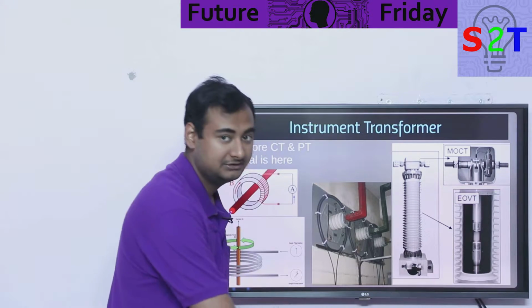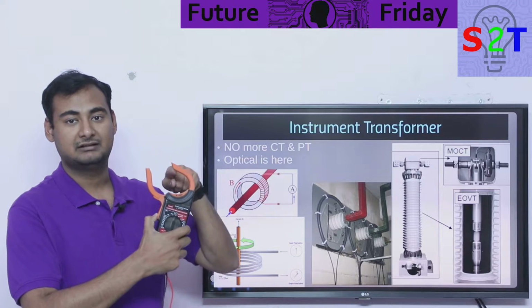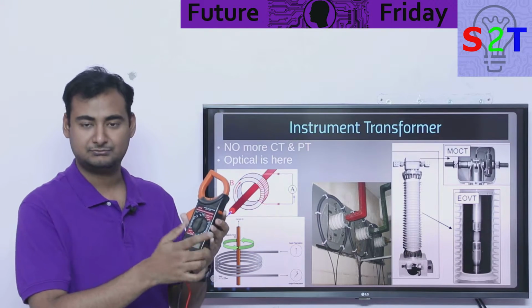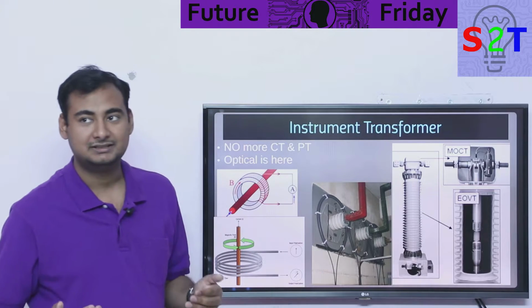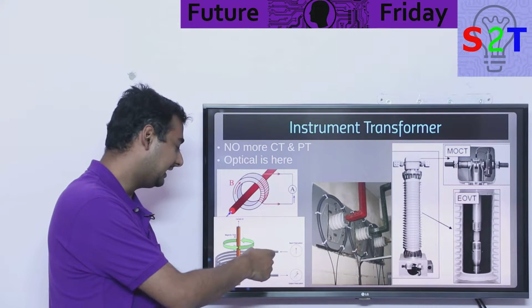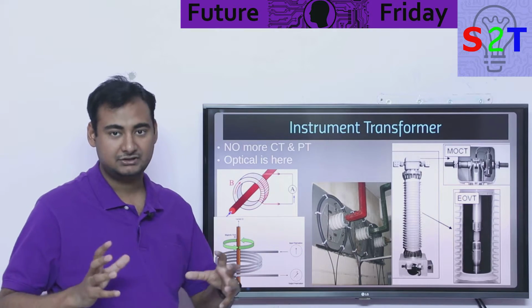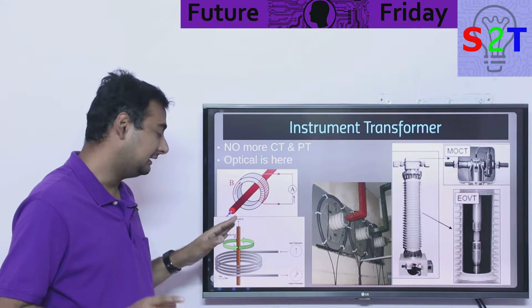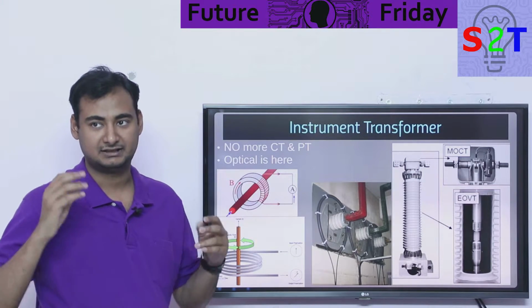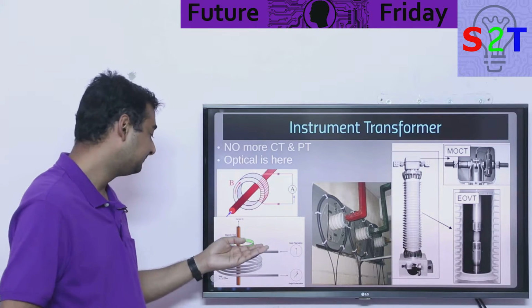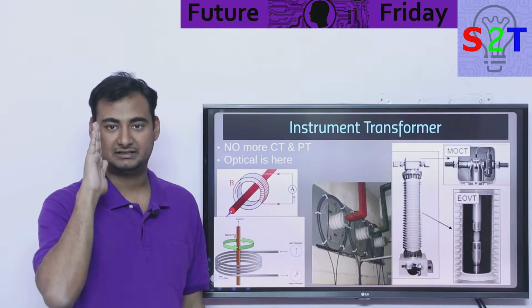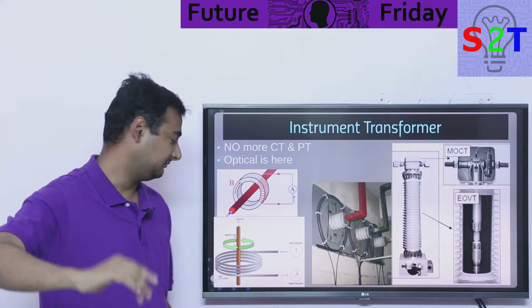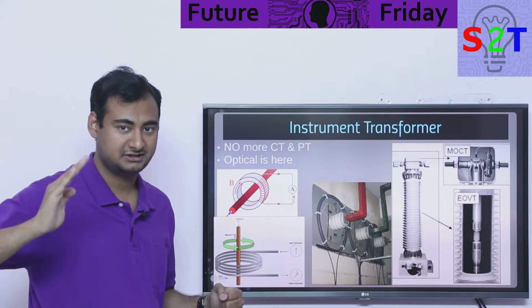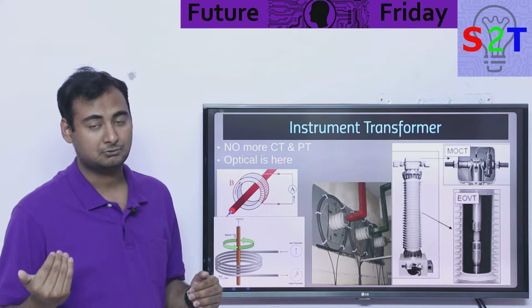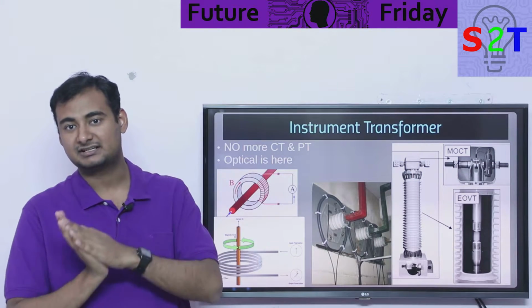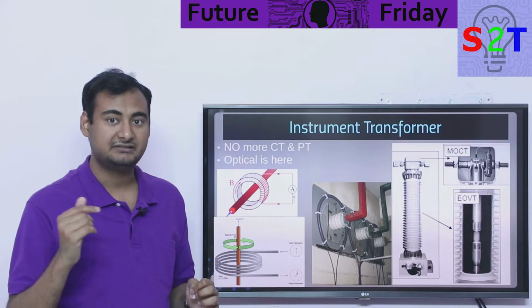If you're familiar with how we measure current, we have a main conductor and you put a coil around it and measure it. Nothing fancy there. But optical, hilariously enough, works in a similar way. We have an optical fiber around the conductor, whatever it is, AC or DC, doesn't matter, and we send polarized light through it, like the light you see in your LCD, and it changes polarity. Let's say the light is going vertically, it gets tilted - the higher the current, the more the tilt. We compare the angles: we sent 90 degrees, we got 75 degrees, now we know the difference, and that difference is the current.